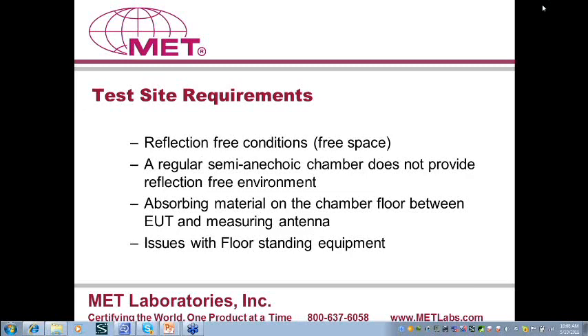At the same time, depending upon the quality of the chamber and the quality of the absorber being used, the challenge was to make the existing chamber work. The existing chamber would normally have absorber which would be good typically only up to one gigahertz. Beyond one gigahertz, their loss characteristics will drastically vary. Therefore, for most labs, they had to go through significant retrofits or upgrades to make those chambers worthy of doing the new CISPR requirements.